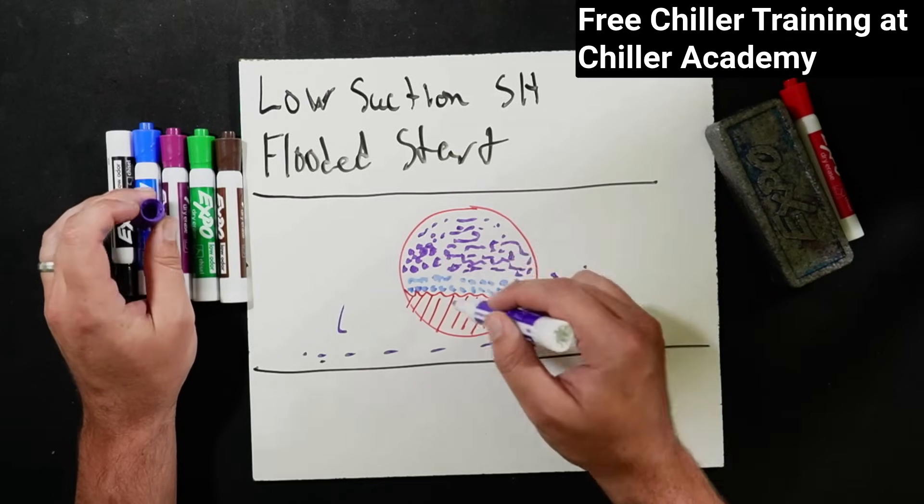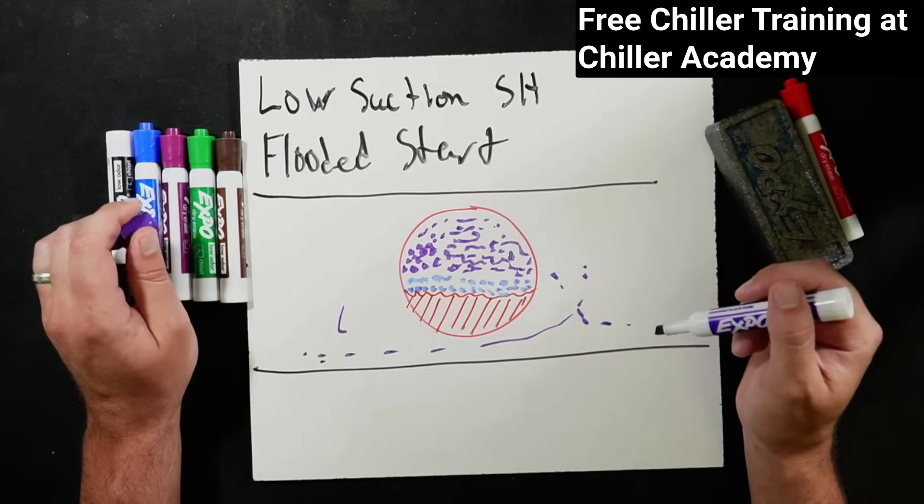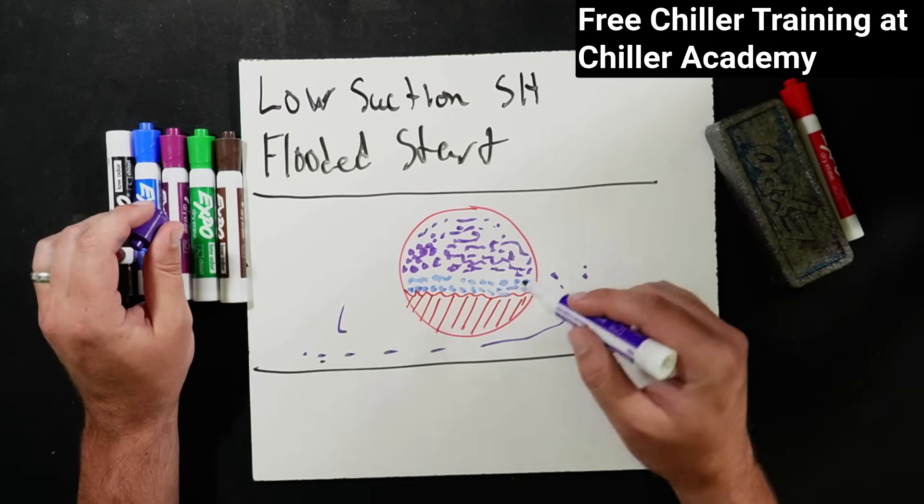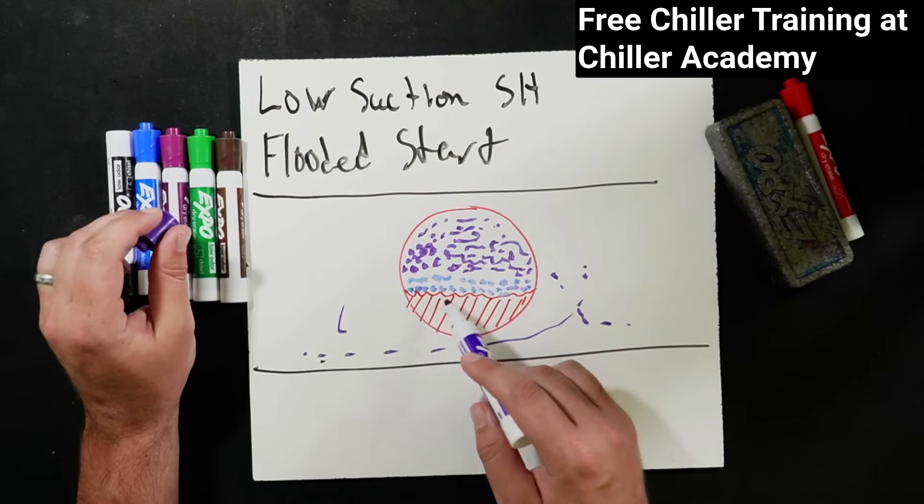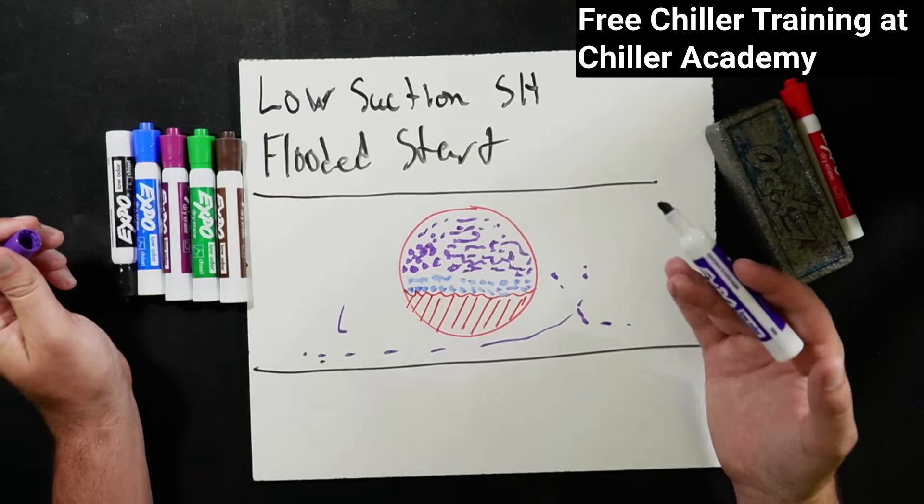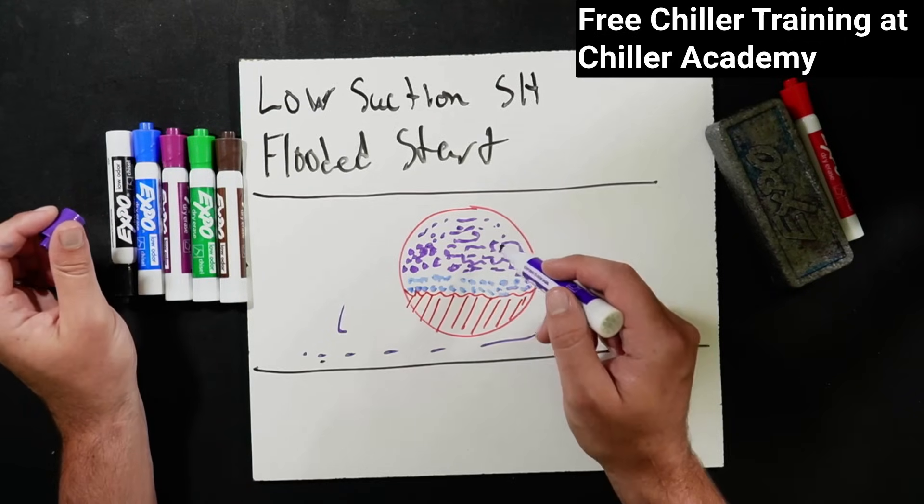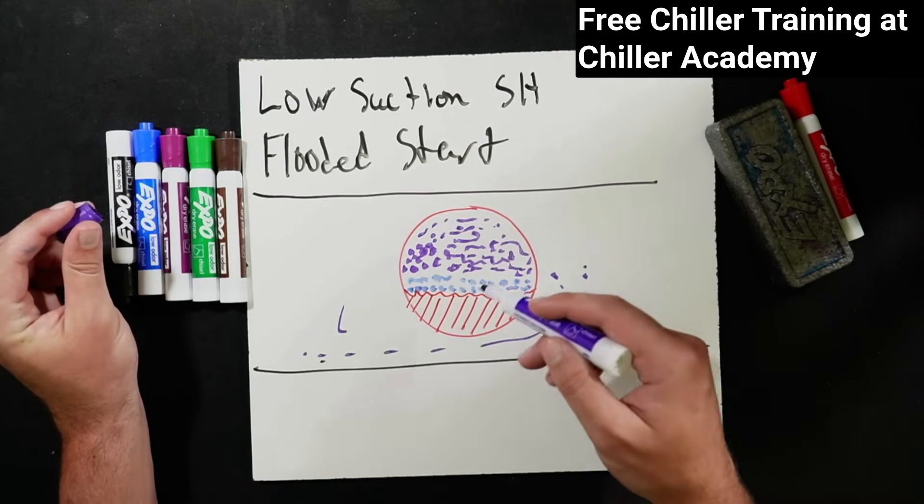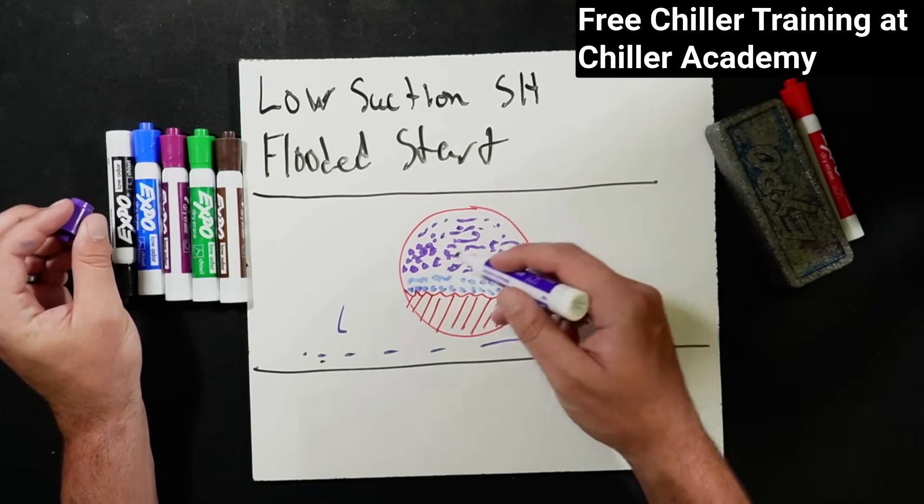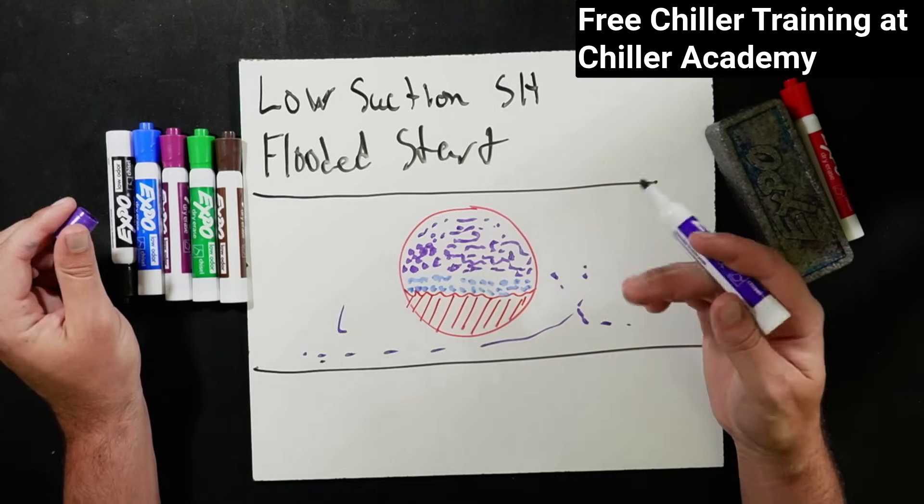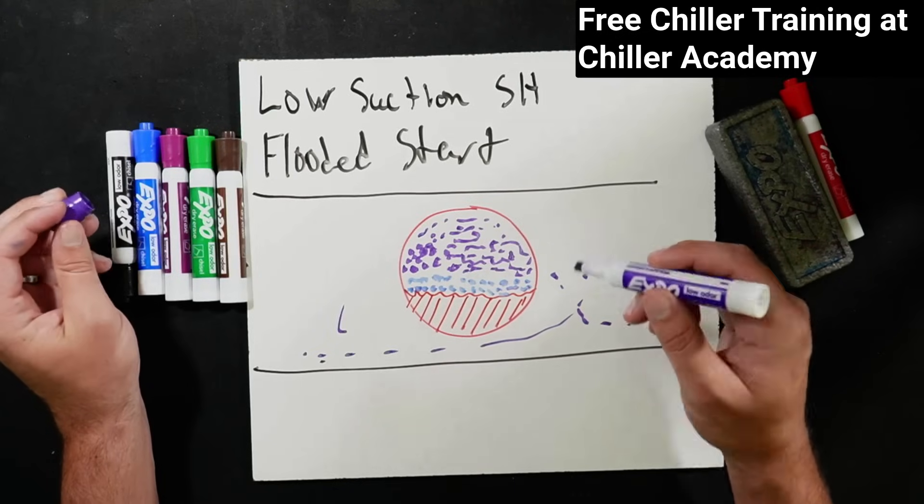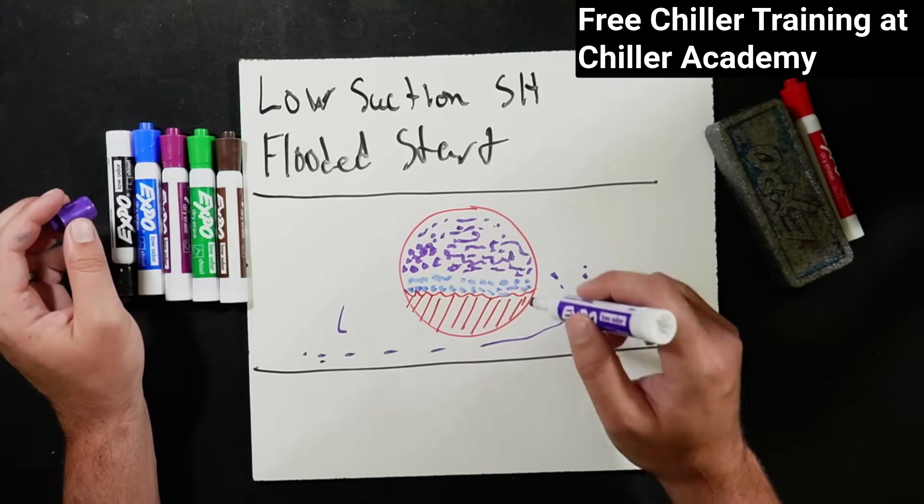Issue number two, you're going to have a major foaming right out the gate. So as soon as that compressor turns on, it's not abnormal to have a little bit happen. What is abnormal is the first several minutes or your sight glass immediately turns to straight heavy foaming. As soon as that compressor cranks up, that is not okay. That is not normal.